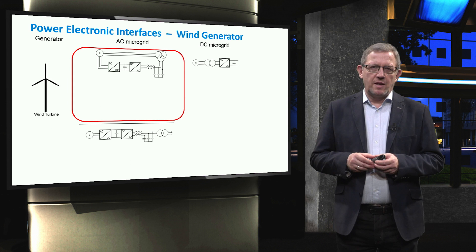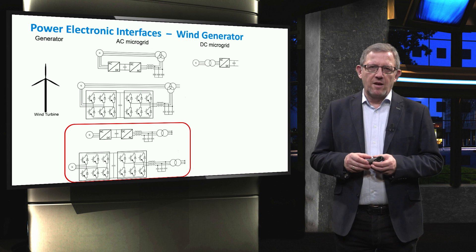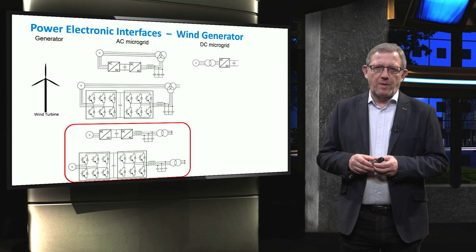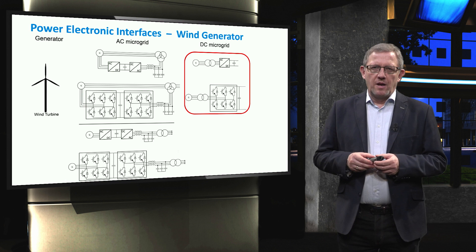In this slide, we show the details of power electronic interfaces including the two back-to-back power converters for a doubly-fed induction generator and a full-scale permanent magnet synchronous generator. Typically one converter is responsible for regulating the DC link voltage and reactive power, while the other controls the active power and the grid voltage. To connect the wind generator to a DC microgrid in the simplest form, a three-phase AC to DC rectifier can also be used.